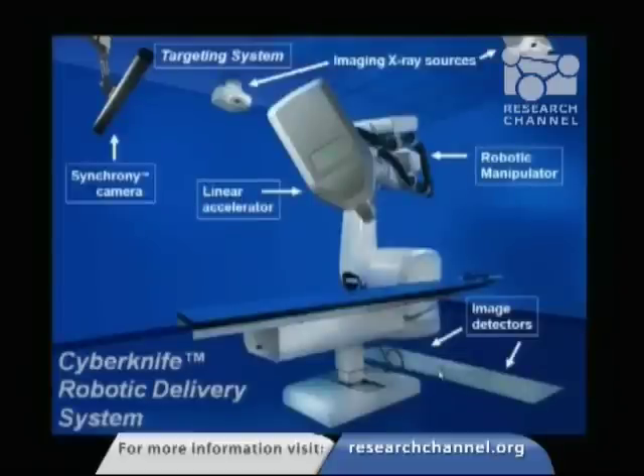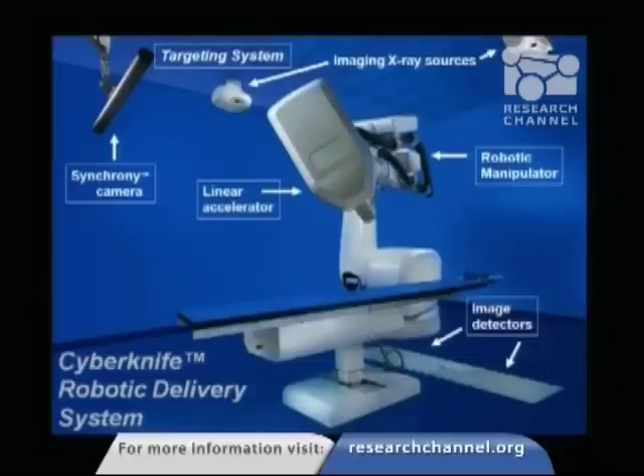This is the CyberKnife that we have today. The main change is that the imagers are placed in the floor, allowing a little more workspace for the robot to achieve different positions. This opens up some of the newer applications we've been using. Essentially, the components of the device are the same.